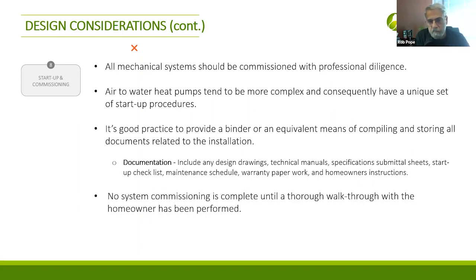That's not good enough. You have to actually go through the system step by step. You have to at least do the manufacturer's required startup procedures, and there's a bunch of other things that should be done, which fall under the category of acceptable standards of practice. Commissioning checks all kinds of stuff.